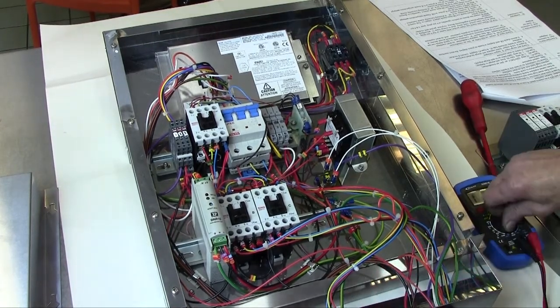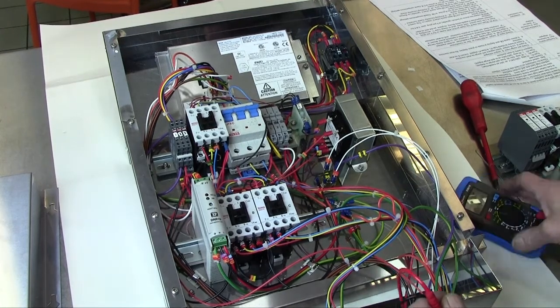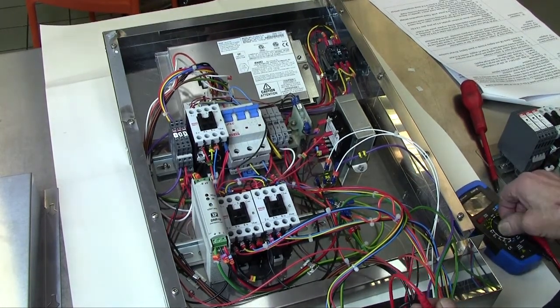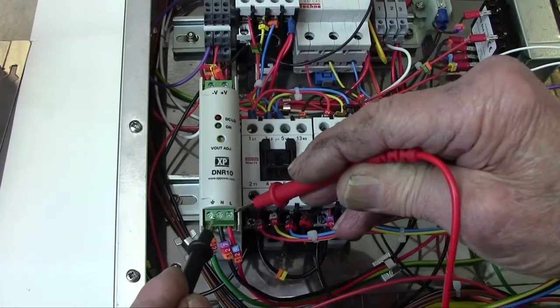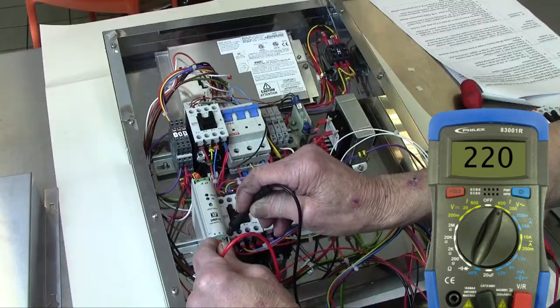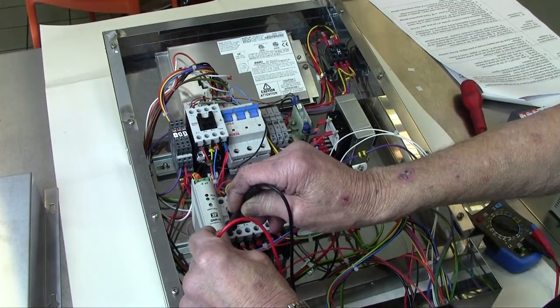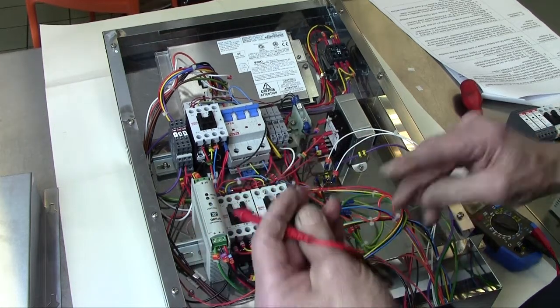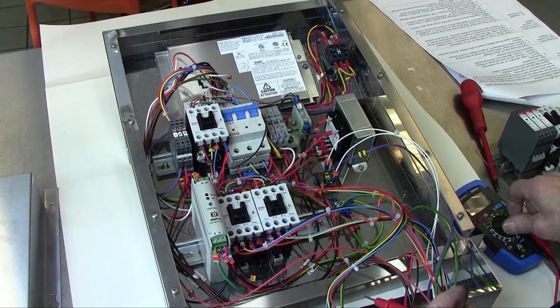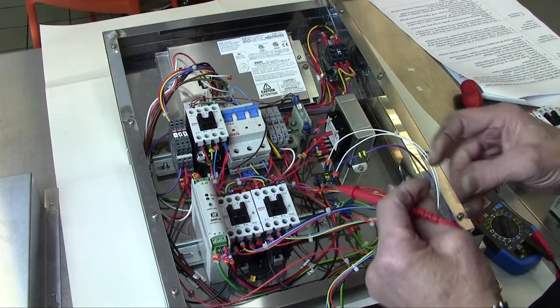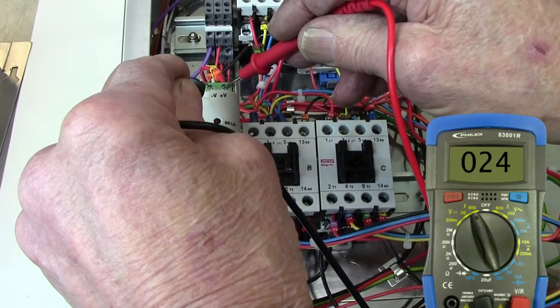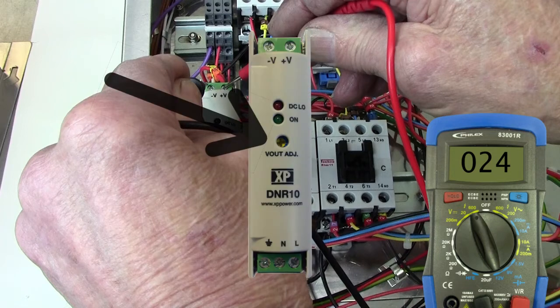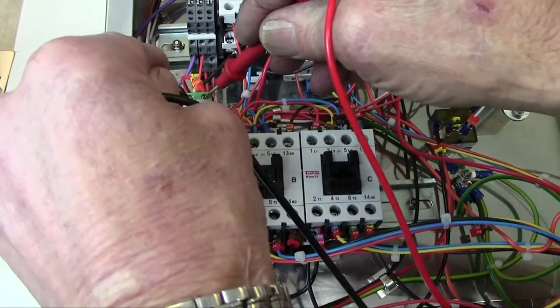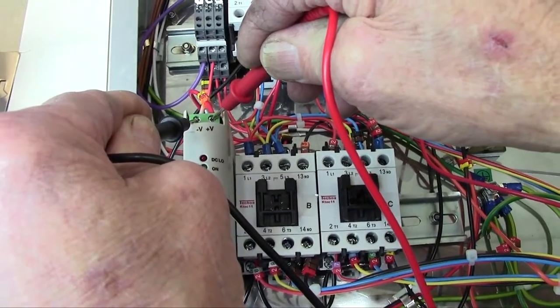The anti-surge input is 220 to 240 volts AC. Set your meter accordingly and check your line and neutral in. If the reading is correct, then go to the other end, but go to DC. Go to DC on your voltmeter and check the outgoing. If the outgoing voltage is less than 24 volts DC, use the voltage adjuster to bring the voltage to a maximum of 24 volt DC. If the outgoing is faulty, replace the anti-surge.